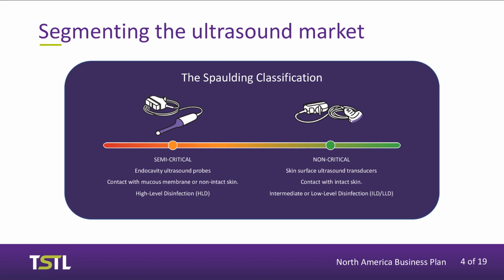The product that we have approved in the United States with another agency, the EPA, is classed as an intermediate level disinfectant. But those instruments that come into contact with the mucosa, the sort of semi-permeable and moist membranes of the body, including the vaginal wall lining or the rectal wall lining, they pose a higher risk and they're defined as semi-critical medical devices and require high-level disinfection. It's a higher grade of disinfection, and the microbiologists have their terminology universally understood as to what the differences are between HLD and ILD or LLD. And the approval that we have received over the weekend is for TRISTEL Alt as a high-level disinfectant for ultrasound probes that are invasive and classified for use on semi-critical medical devices.